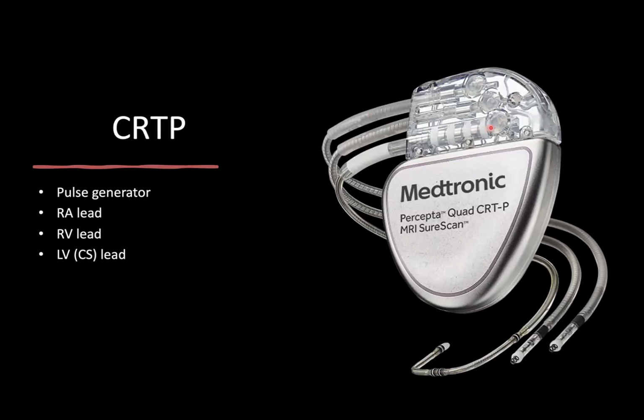I just want to point out that the header for an IS4 lead, IS4 meaning quadrupolar, looks like this. It looks not very dissimilar to the header for a DF4, which we'll discuss later. And then you've got the two bipolar lead placement positions for the device.